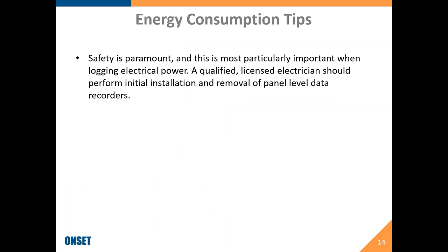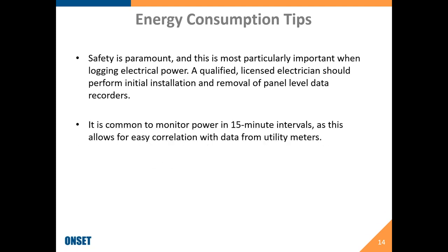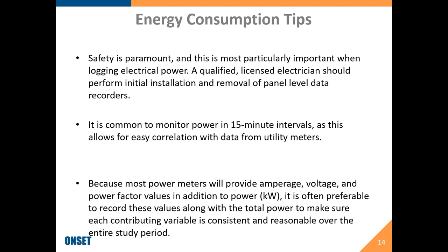As I mentioned earlier, with all of our energy units, safety is the most important thing. If you're doing anything at a panel level, please do make sure to have a licensed electrician perform the installation. It's common to monitor power in 15-minute intervals. That really will be the easiest way to match up the data that you're collecting with any utility meters or other devices that are already deployed in the field.